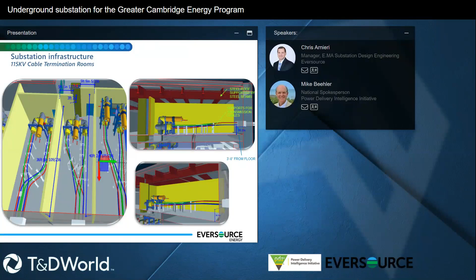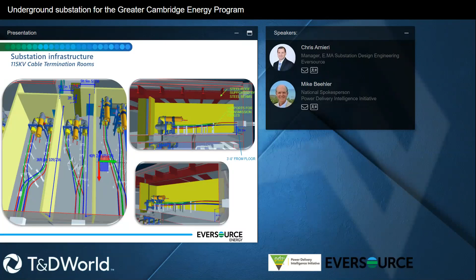In the event of a catastrophic failure on the transmission line, it wouldn't take out any other transmission duct bank grouping. But also, since they're removable, after the event, if we needed to re-pull, we could remove the wall to gain the additional space required to pull the cables back in and remake the connections to the gas insulated bus.